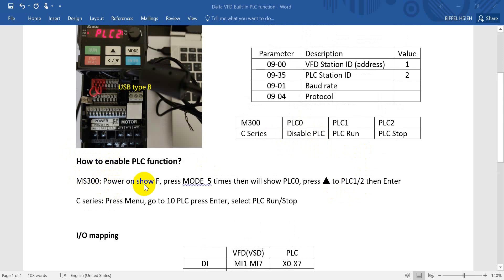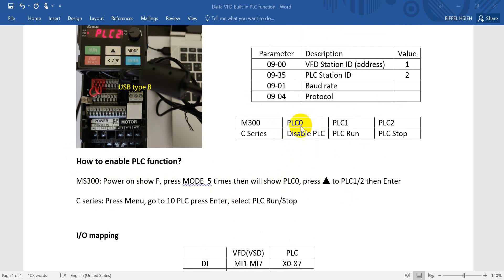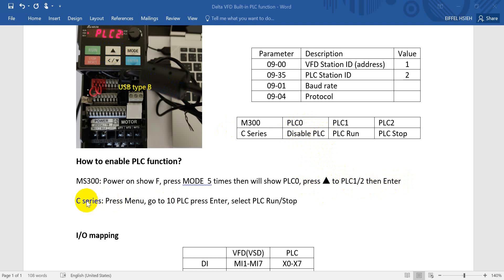And this one already mentioned here. You can see once we power on, actually it will show the frequency, and you can press MODE button five times until it shows PLC0. But as you know, PLC0 is disabled PLC function, so you can press the upper button to PLC1 or PLC2, then press Enter. And for C series, you can press the Menu and go to item 10 PLC and press Enter, then select PLC run or PLC stop, and then press Enter.